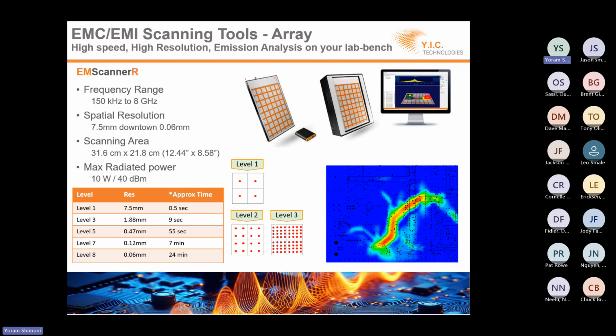We have this scanner, which is the EMS, and we have this one, which is the R version, which stands for high resolution. For this scanner, the resolution is 7.5 millimeters. That's the physical distance between the antennas. I thought I had a picture here of the boards, maybe in the next slide or so. So we can actually make measurements 7.5 millimeters apart. In the high resolution, we place that board on a set of XY motors, essentially rails, and we can precisely move that board. So each 7.5 millimeter cell here, we divide in two on each axis, and we can make four measurements.